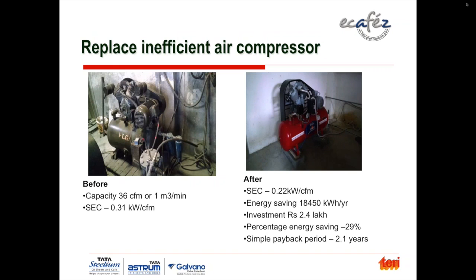Now this example is again very commonly found in SMEs: an inefficient air compressor. It is a smaller air compressor, 36 CFM. The specific energy consumption of this compressor, as measured, was 0.31 units of electricity per CFM. The new air compressor which was recommended has a specific energy consumption of 0.22 units of electricity per CFM. It's an LG air compressor.